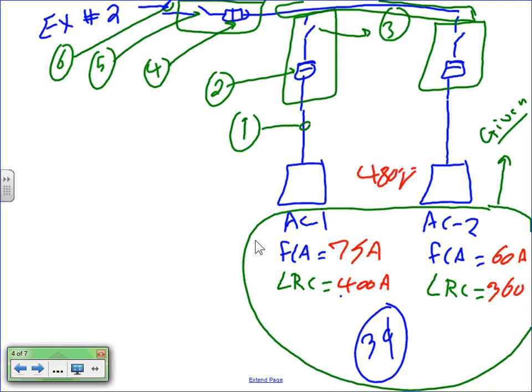Number 2 is the overcurrent protection device. Number 3 is the disconnect, the branch circuit disconnect. Number 4, the feeder overcurrent protection device. Number 5 is the disconnect for the whole system. And number 6 is the feeder for the whole system. Can I have thumbs up to know that we fully understand what we're looking at here, the one-line diagram? Guys, being engineers and designers, our start point is always called a riser or a one-line diagram. What you're looking at is a one-line diagram of the system, how the system is put together. And then we're supposed to fill in the information, give it to the electrician, they go install it, right?